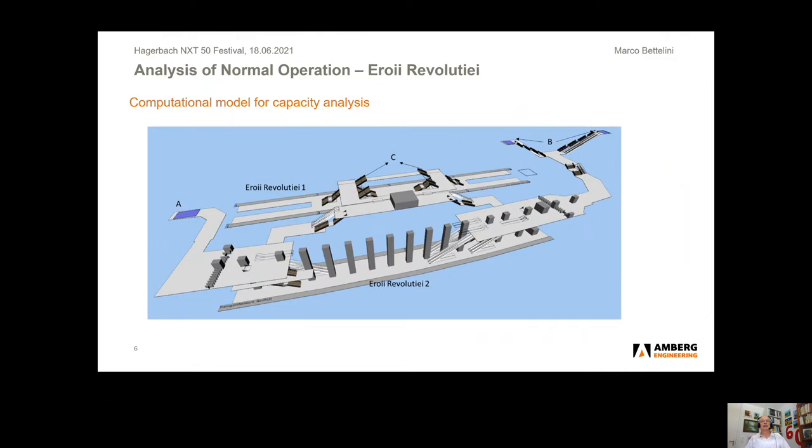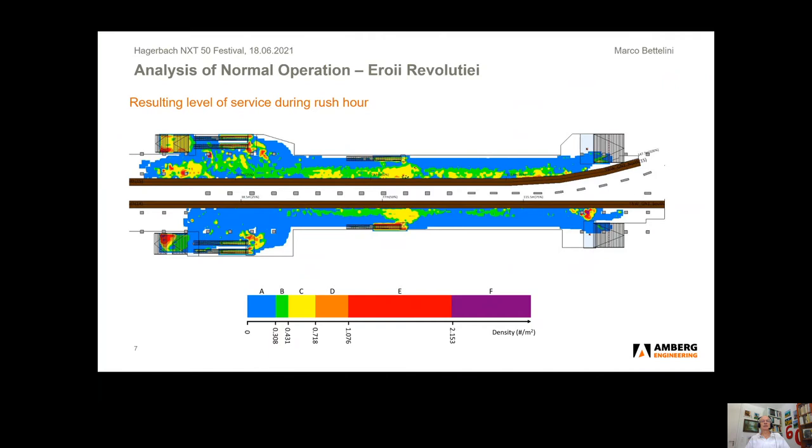The analysis of fire safety begins with normal operation. We see here a computational model for the station Eroii Revolutiei in Bucharest. This is the kind of model we use for analyzing person fluxes in normal operation and system capacity. In this picture, you see the maximum person concentration at track level at peak time. The yellow component shows person concentration up to 0.7 persons per square meter — quite a large concentration. This represents the starting point for safety configuration. If a fire happens, we have to manage all these persons and bring them to safety.